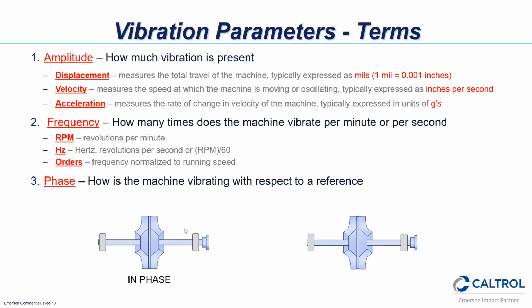Phase analysis is also something we look at. We're measuring two planes here, but we're getting a phase angle off of those, and that helps us determine, every piece of equipment when it's moving moves at a certain phase angle. When we're balancing, we use those phase angles to determine where to put weights on. In a bearing, a lot of times, if we're determining the imbalance, and if it's in phase, that means we would affect both ends of this fan wheel at the same angle. Sometimes they're out of phase with each other. So if you put your accelerometer on both at the same angles, you may get a 180 shift out of that, which is called a couple imbalance.